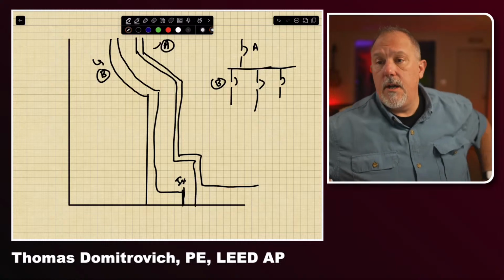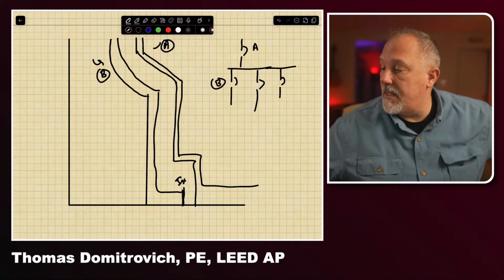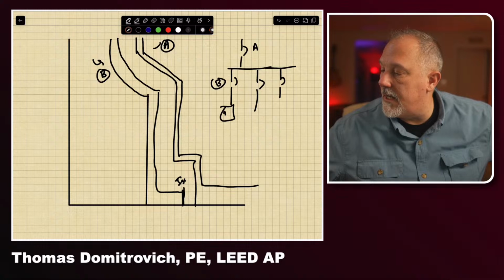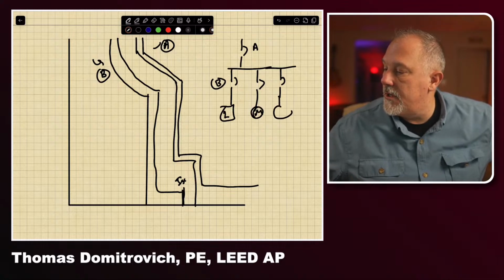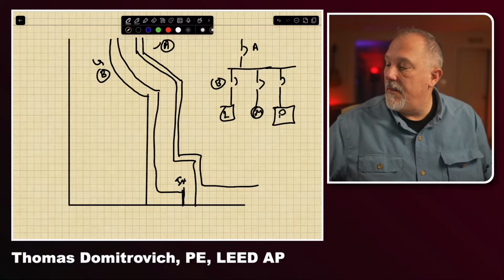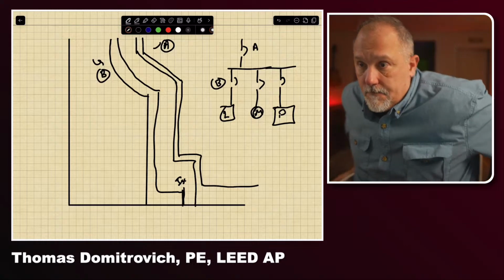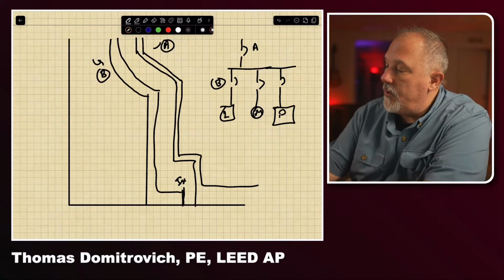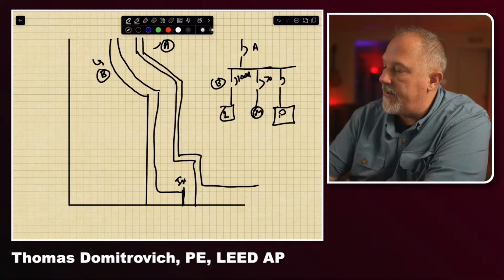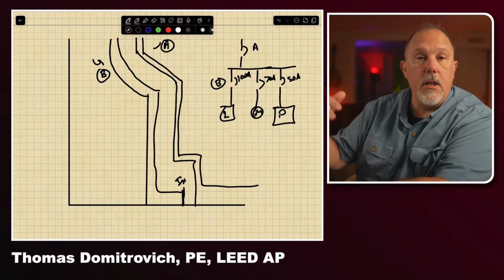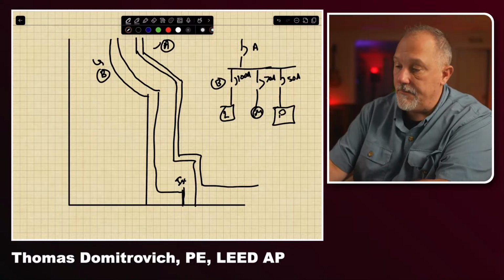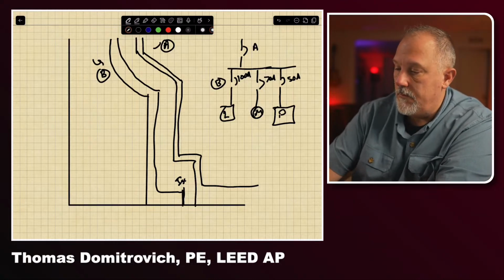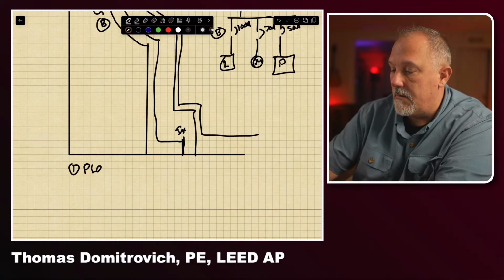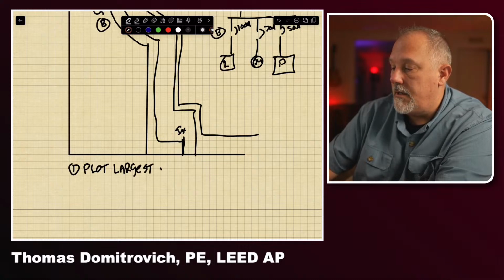Now, what we would typically do, Bill, is breaker B is, say, a branch. Say this is, I don't know, we'll call this L for lighting. We'll put M for motors. And we'll put a square box, and we'll call this control panel, industrial control panels. And let's say that breaker B, what we would typically do if you're doing a selective coordination study and you're looking at a scenario like this, you would pick, let's say that this is 100 amp and this is 70 amp and this is 50 amp. You would pick the largest breaker downstream and you would plot that. So one plot, largest downstream breaker.